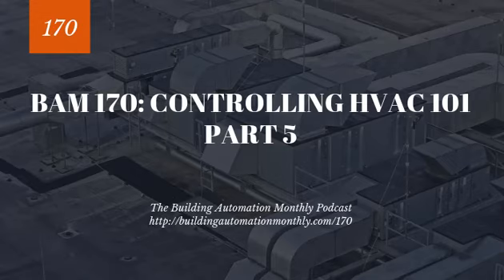Now, with the mixing valve, you're going to typically be controlling off of differential pressure and set point. As I said, the pressure sensor is typically at the end of the run, and you're going to be maintaining that pressure drop. So you're going to want to make sure that you're providing adequate pressure so that you have the optimal flow to get the proper exchange through the coil on the different airside systems. All right, making sense so far?